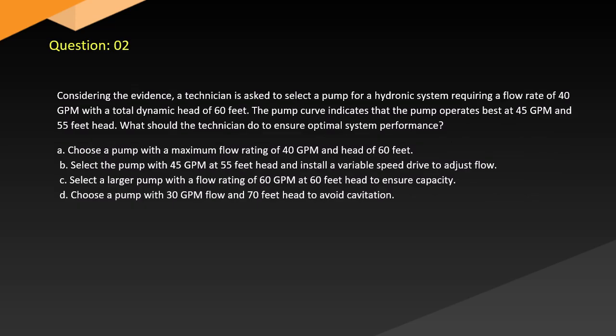Question 2. Considering the evidence, a technician is asked to select a pump for a hydronic system requiring a flow rate of 40 GPM with a total dynamic head of 60 feet. The pump curve indicates that the pump operates best at 45 GPM and 55 feet head. What should the technician do to ensure optimal system performance?